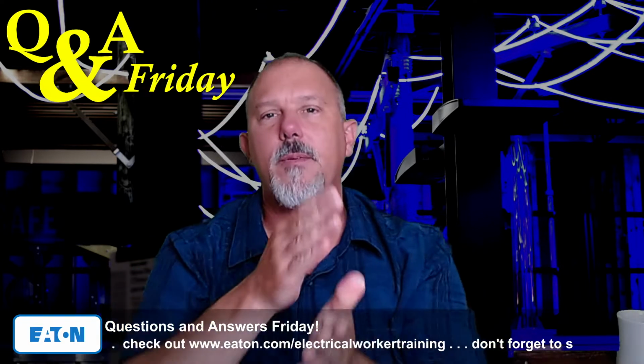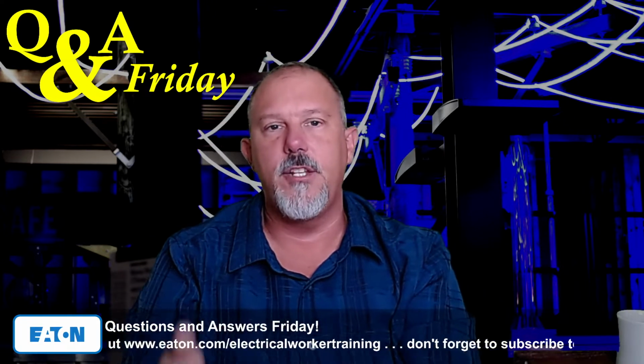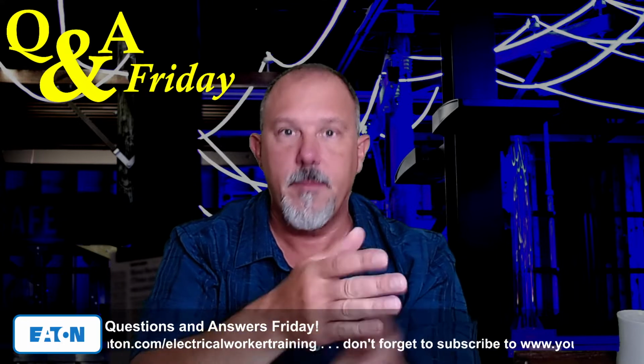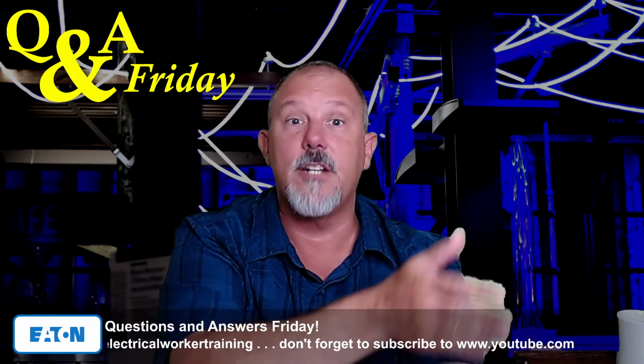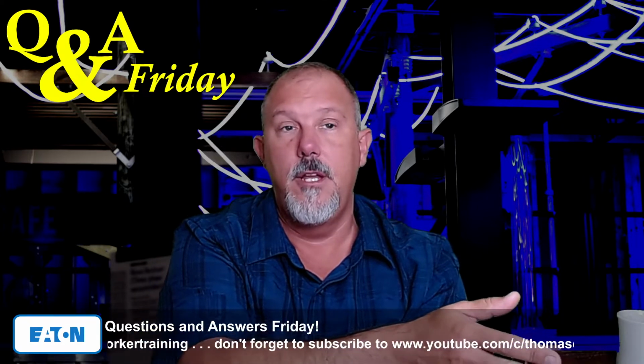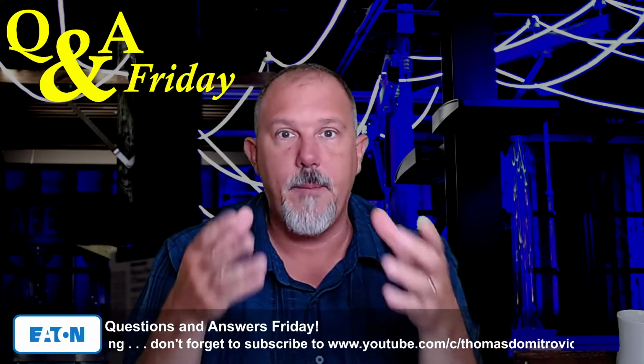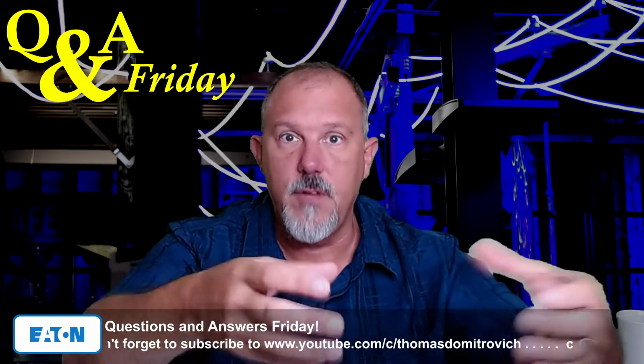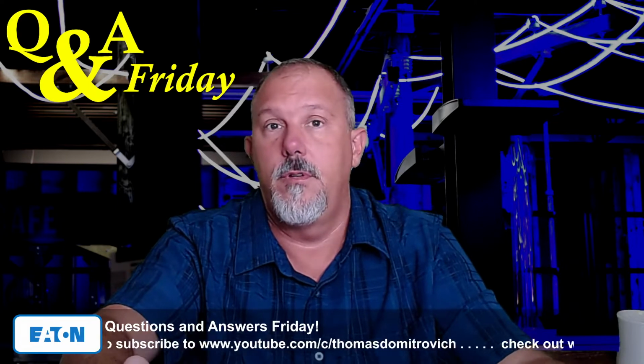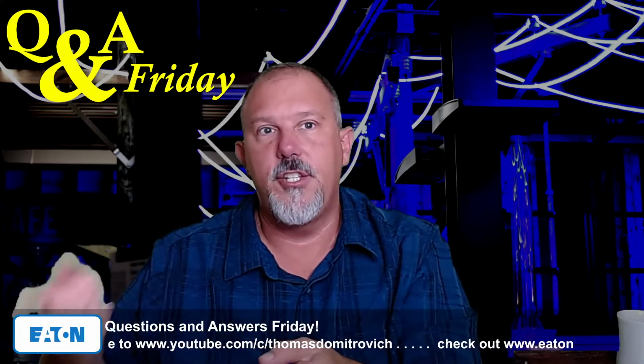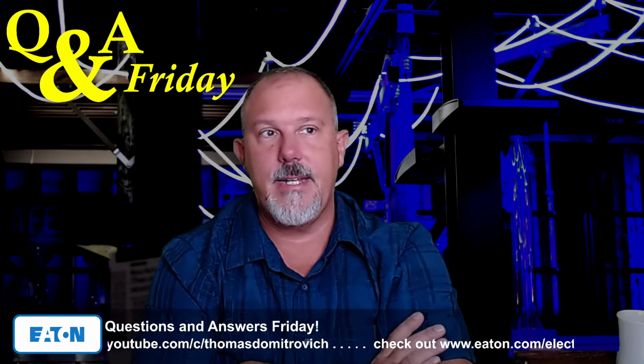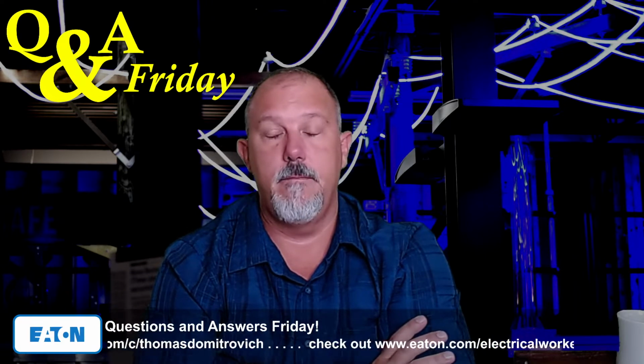Yeah, Ryan, but remember, he's taking a 1200 amp breaker and adjusting it lower to protect the conductor at its ampacity. So if I have 100 amps worth of ampacity and I have 100 amps of continuous load, and I have it on a 1200 amp breaker and I adjust it down to 100, I'm protecting that conductor at its ampacity.